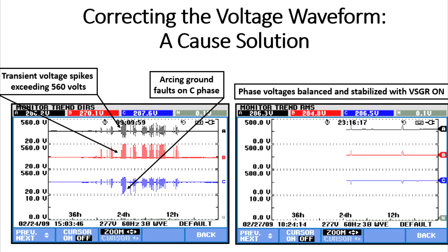On the right, we see what happens when you can stabilize and balance your voltages. You can see a couple of events that have attempted to happen. However, the arcing ground fault has been prevented. We've eliminated the arc flash hazard that could be there. And best of all, the equipment ran completely problem-free and still is to this day.